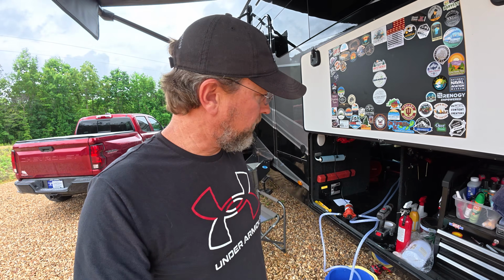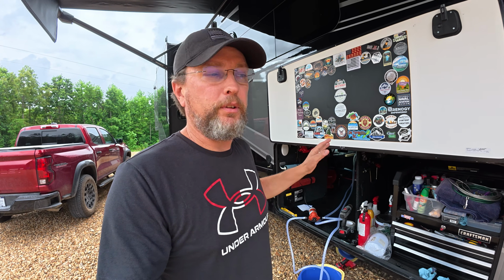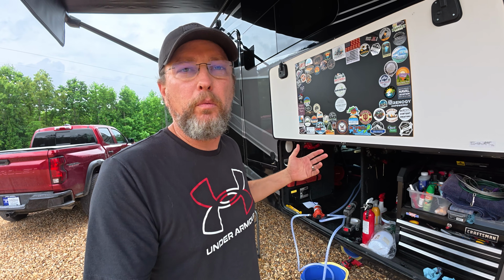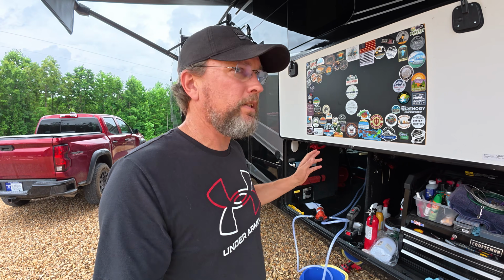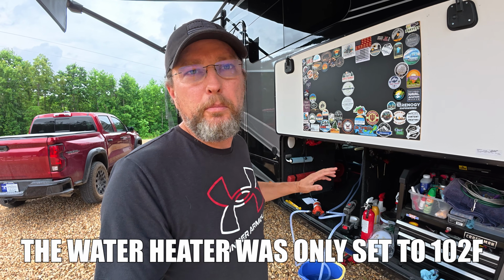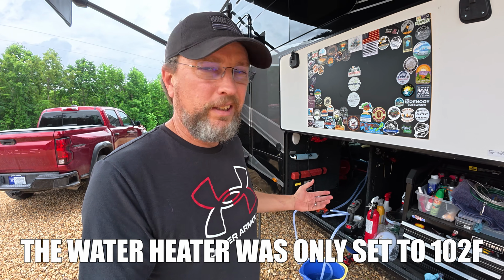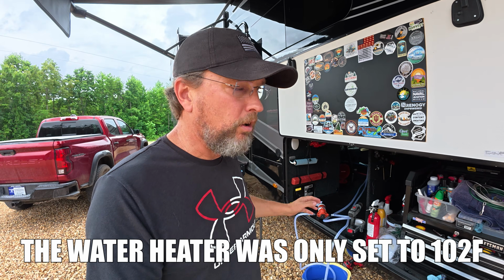Full disclosure: remember when I said the first step is to turn the water off and depressurize the system? Well, what should go along with that is also turning off the water heater itself, because as soon as you put flow through it, it's going to start up and heat the vinegar. This probably ran for a couple of minutes with the water heater on before I realized what was going on. I don't think it'll hurt anything since it didn't run that long with the water heater on, but remember to turn the water heater off before putting water through it.